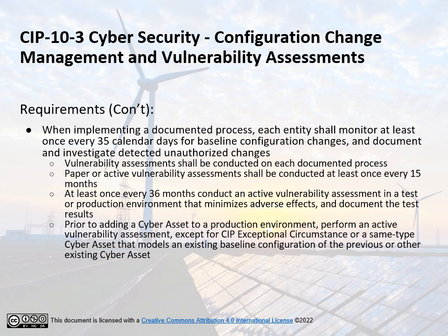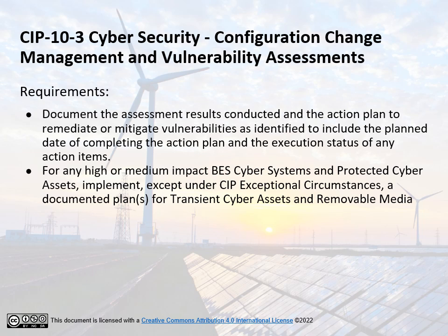Prior to adding a cyber asset to a production environment, perform an active vulnerability assessment except for CIP exceptional circumstances or a same type cyber asset that models an existing baseline configuration of the previous or other existing cyber asset. CIP-010-3 Configuration Change Management Vulnerability Assessments. Requirements: document the assessment results conducted in the action plan to remediate or mitigate vulnerabilities as identified to include the planned date of completing the action plan and the execution status of any action items. For any high or medium impact BES cyber systems and protected cyber assets, implement, except under CIP exceptional circumstances, a documented plan for transient cyber assets and removable media, also known as USB sticks.